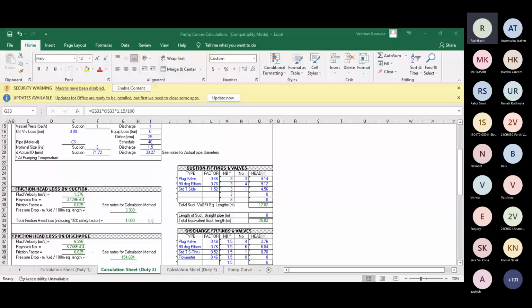So there is on one side a globe valve and on other side there is a 3-inch pipeline with 10 meter of length. So globe valve में जो pressure drop होगा, that pressure drop will be equal to a pressure drop that is created in a 3-inch diameter and 10 meter of length of pipe. So उसको हमने क्या किया, globe valve का जो pressure drop था उसको equivalent length of pipeline में convert किया. Is it clear? Yes or no? Yes sir, clear.